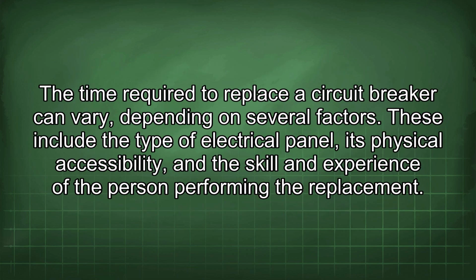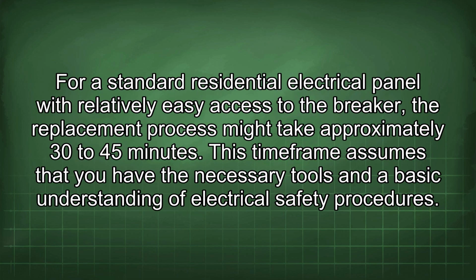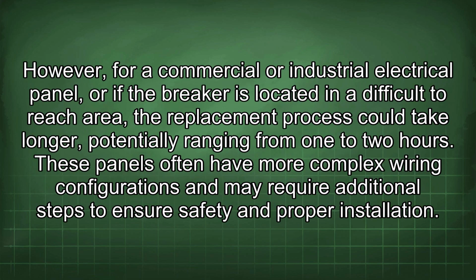that it receives power. The time required to replace a circuit breaker can vary depending on several factors. These include the type of electrical panel, its physical accessibility, and the skill and experience of the person performing the replacement. For a standard residential electrical panel with relatively easy access to the breaker, the replacement process might take approximately 30 to 45 minutes. This time frame assumes that you have the necessary tools and a basic understanding of electrical safety procedures. However, for a commercial or industrial electrical panel, or if the breaker is located in a difficult-to-reach area, the replacement process could take longer, potentially ranging from 1 to 2 hours. These panels often have more complex wiring configurations and may require additional steps to ensure safety and proper installation.